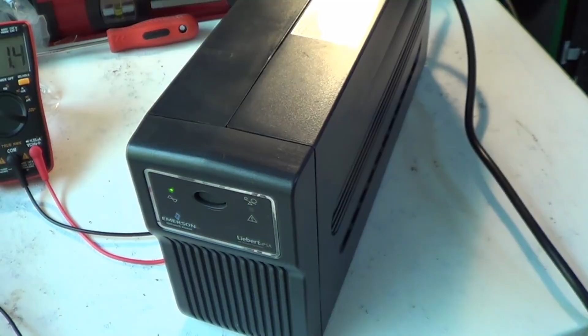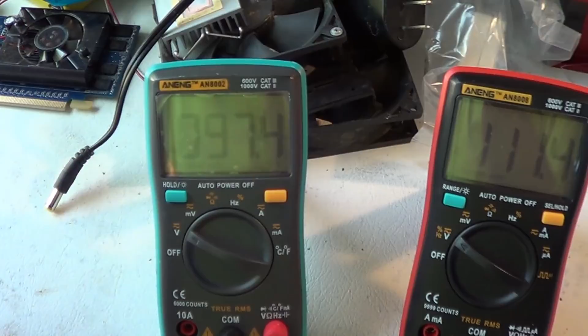This thing has not gone to battery. It contains an auto transformer of its own, and it just switched in a winding with a relay to boost the low line voltage. We're sitting at about 97 volts coming out of the auto transformer. We have about 111 coming out of the UPS. If we drop it much lower than that - there it went to battery.